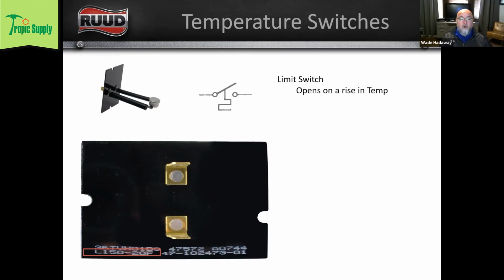If you have a furnace that's overheating, you're either overfiring the gas valve or you've got airflow problems. Don't take a switch that opens at 150 and closes at 130 and replace it with a switch that opens at 200. Figure out why your switch is opening. I don't know, this is not an airflow class, but I think it bears repeating.